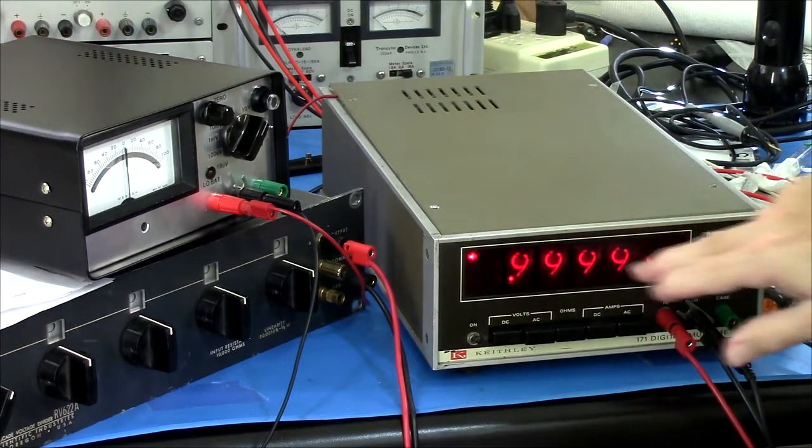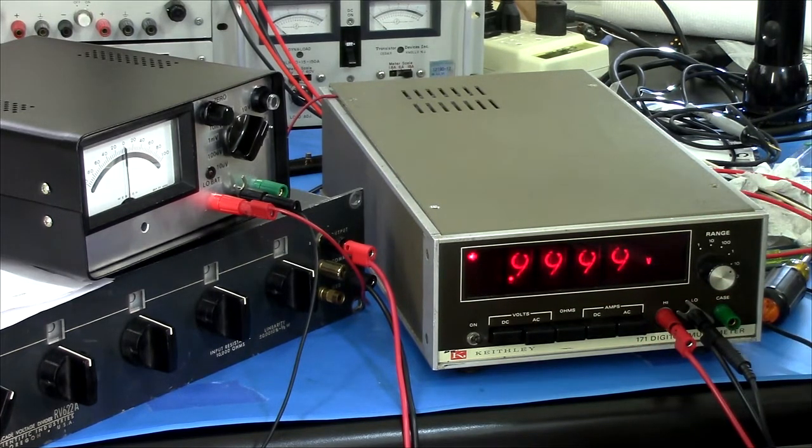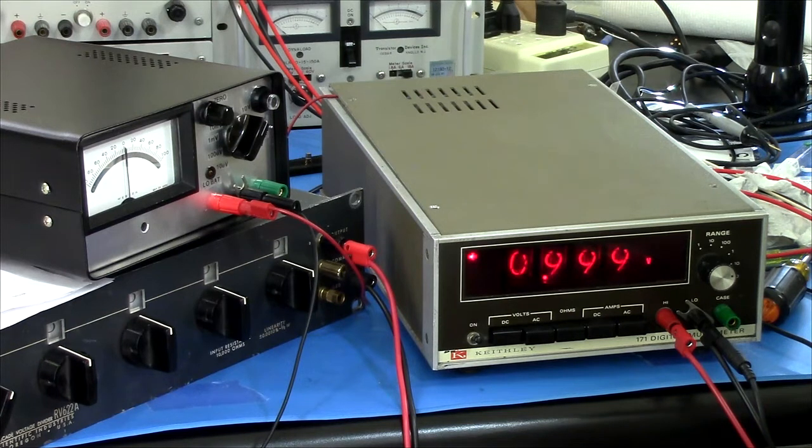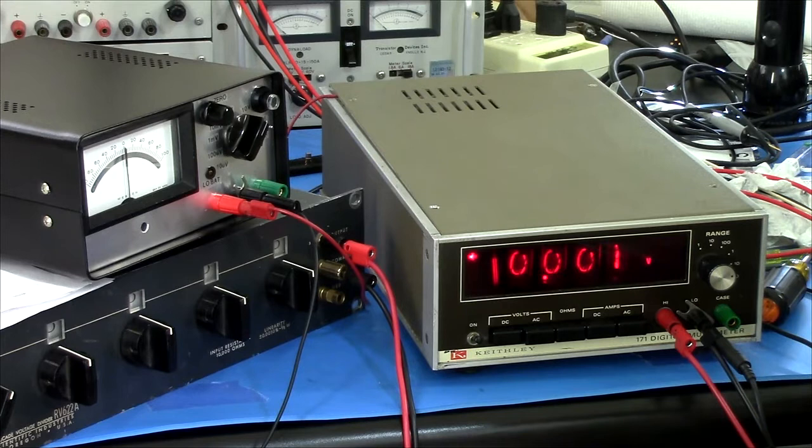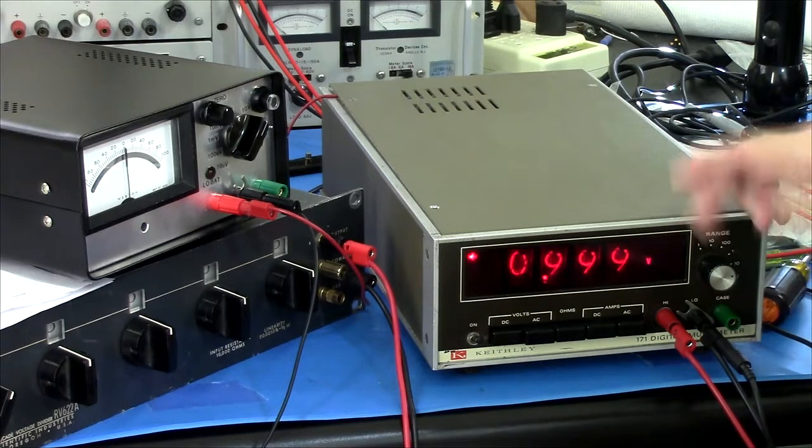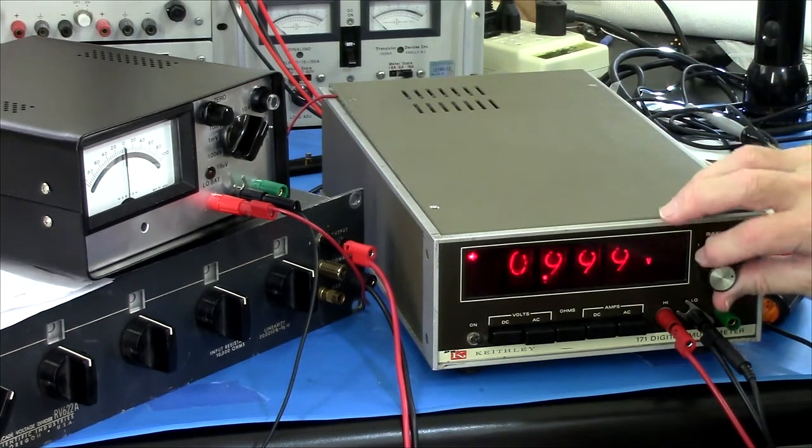I'm on the one-volt scale, I'm putting one volt in. That's pretty good right there, 0.9999, within one count. If I go to the 10-volt scale, I can give it 10 volts in. It's within one count there. So we'll go back to one. There's one volt on the 10-volt scale, it's within a count or two. That's pretty good.